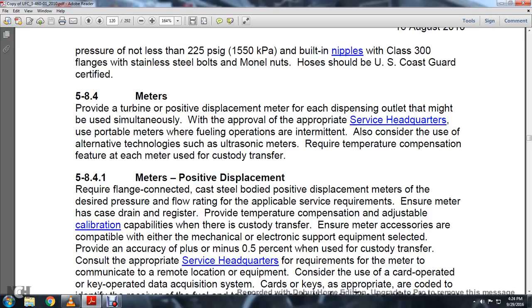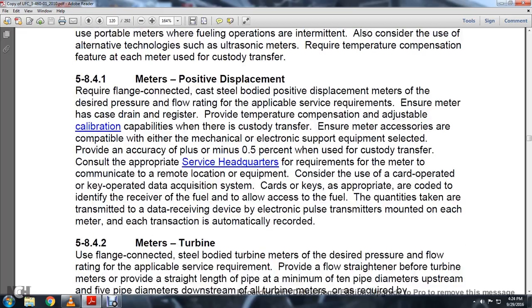5.8.4 meters. Provide turbine or positive displacement meters at the dispensing outlet, to be used simultaneously, with approval of the appropriate service headquarters for portable meters where the fueling operations are intermittent. Also consider the use of alternative technology such as ultrasonic meters that require temperature compensation feature at each meter used for custody transfer.